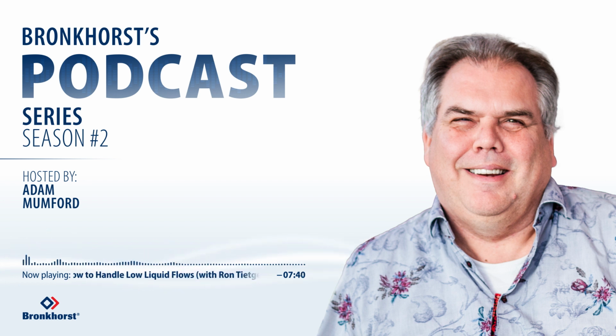The downfall is that this can be used very well with liquid applications. For gas applications, it's not recommended because of the accuracy of the density measurement for gas instruments. You can imagine the total accuracy when you have a variation of 1 kilogram per cubic meter in liquid. Liquids have a density which is close to 1,000 kilogram per cubic meter. A gas has a density of only 1 kilogram per cubic meter. So for gas instruments, volumetric flow with a Coriolis is not a very good option. But for liquid instruments, it's no problem at all. Awesome. I think that answers that.